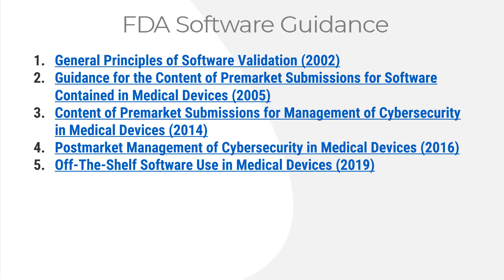The first guidance document is General Principles of Software Validation, a 2002 document. Much of its content is repeated in the second guidance document from 2005, which covers the content of pre-market submissions for software contained in medical devices. Whether you have a device with hardware and software or you have software as a medical device, this is what the FDA wants to see when you submit a pre-market notification or 510(k) submission.